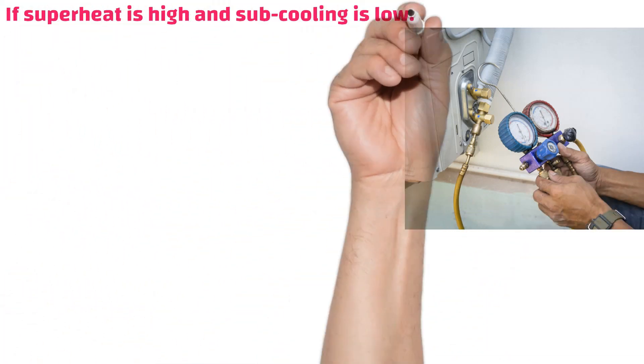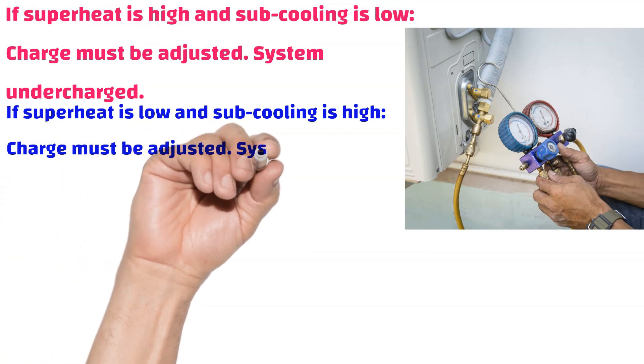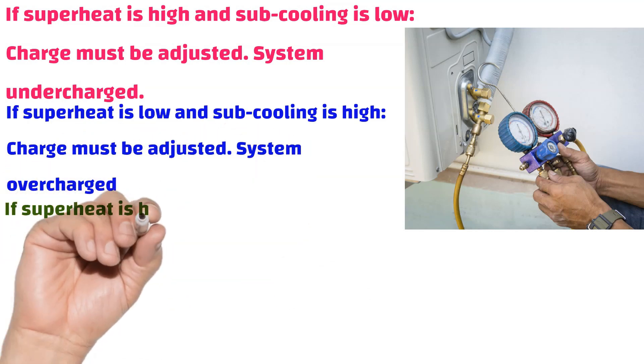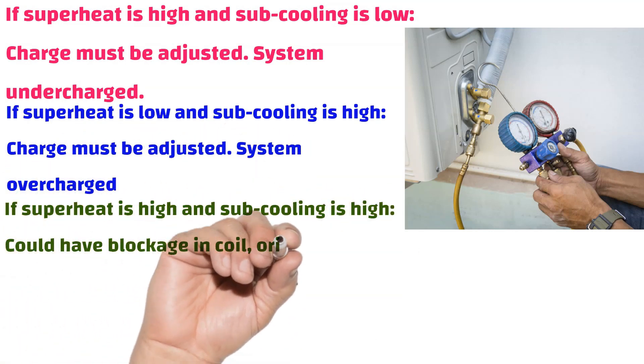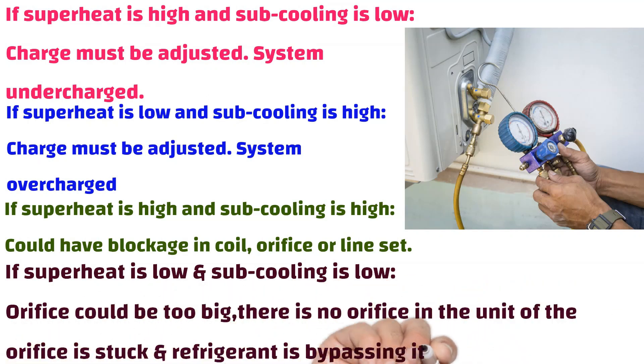If superheat is high and sub-cooling is low, charge must be adjusted — the system is undercharged. If superheat is low and sub-cooling is high, charge must be adjusted — the system is overcharged. If superheat is high and sub-cooling is high, there could be a blockage in the coil, orifice, or line set. If superheat is low and sub-cooling is low, the orifice could be too big, there is no orifice, or refrigerant is bypassing it.